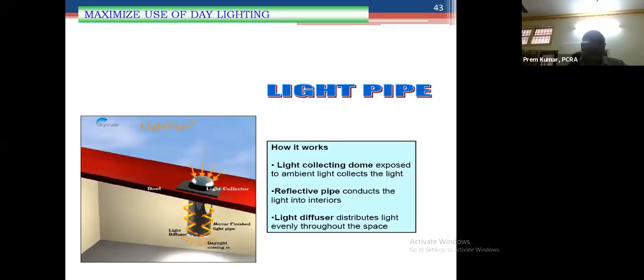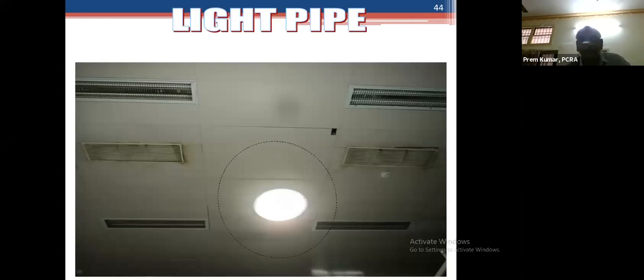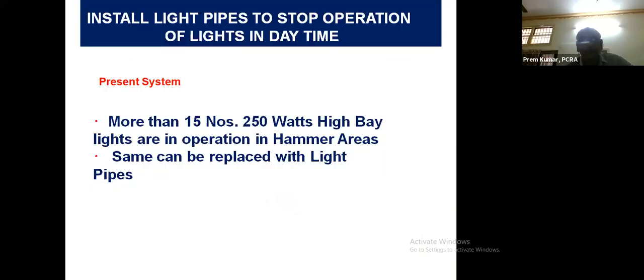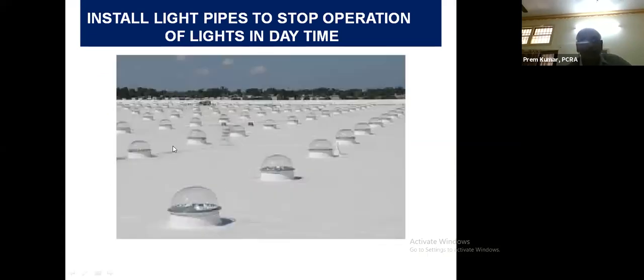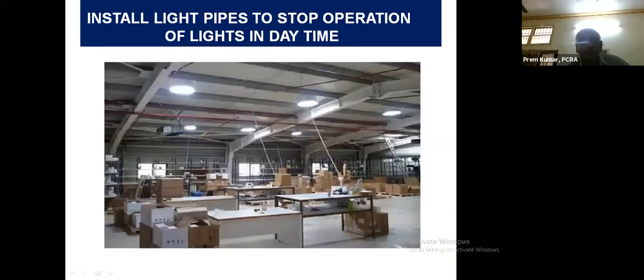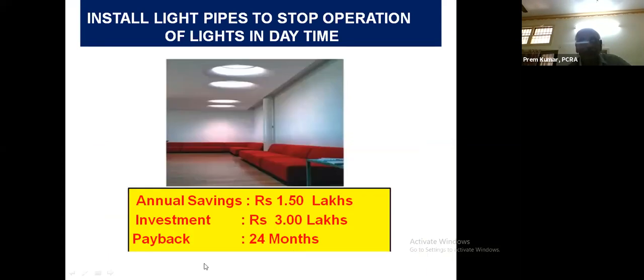So the next option is the light pipe. The solar pipe uses natural lighting to bring natural light to the shop floor, so that the artificial lighting can be switched off during the day. We will see one or two cases. This is a site which has daylighting in a workshop. The workshop was using 15 numbers of 250 watt high bay lights. So they installed it, and it appears like this. The payback was around 24 months.